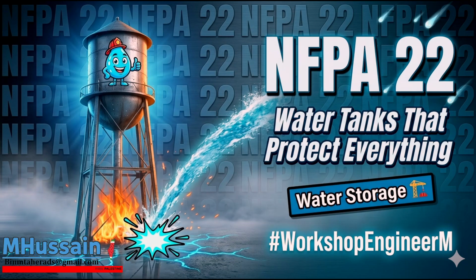They always do. Finally, let's discuss the valving on elevated tanks. Section 14.2.11 mandates that check valves must be placed horizontally in a pit underneath the tank or safely protected on the ground floor. They cannot be installed vertically in the riser pipe 50 or 100 feet in the air. That rule is driven entirely by maintenance safety and hydrostatic head pressure. A check valve for a large fire main is a massive, heavy mechanical device containing a large metal clapper assembly designed to prevent water from flowing backward.